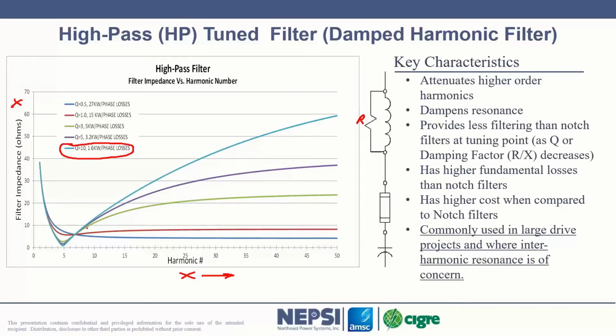So to some degree, as you lower the value of R, it becomes a notch filter, which means that the calculations required to calculate X of C and X of L here are basically the same. The only thing that changes is we're adding a value of resistance, which determines the shape of the impedance curve. But the tuning point is always calculated the same, whether it's a high pass, C high pass, or a notch filter.